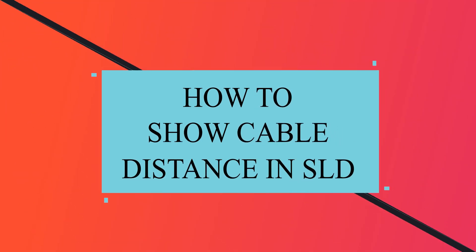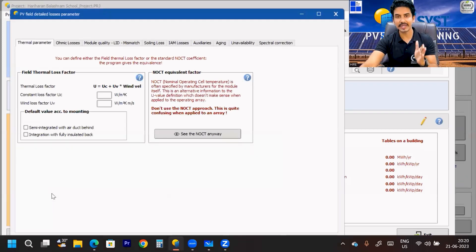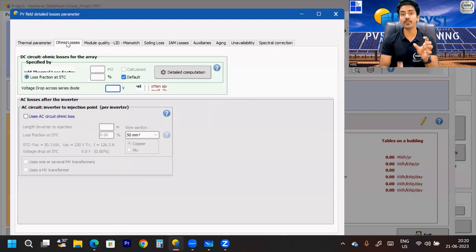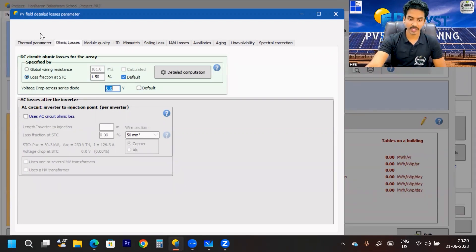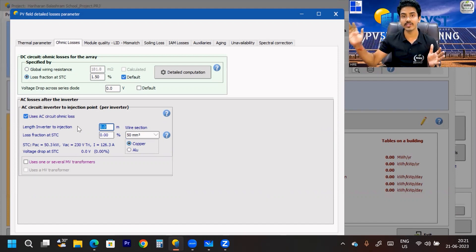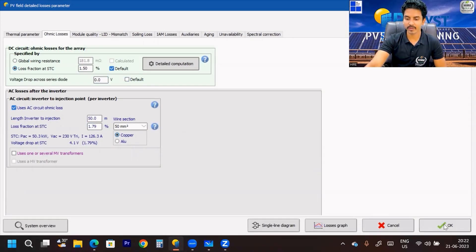Now that we're done with the system part, we move to Detail Losses. How to consider thermal loss and other losses I have described in a previous video — there are two sessions for detail losses you can check. To mention the cable distance or cable size you need to calculate the ohmic losses. For AC loss, I am considering a distance of 50 meters from inverter to injection point. For a 50 sq mm copper cable, the loss is around 1.79%, which is fine. I click OK.